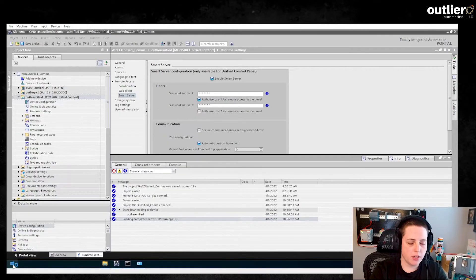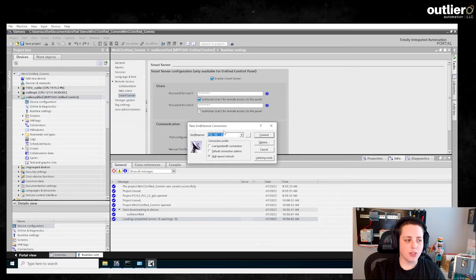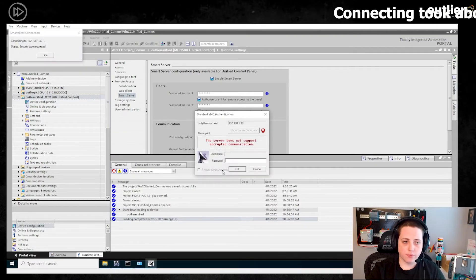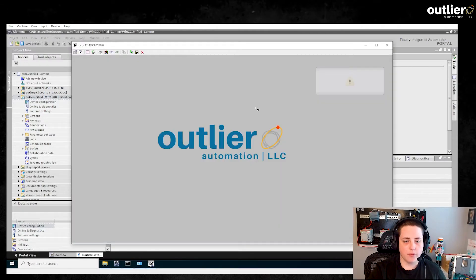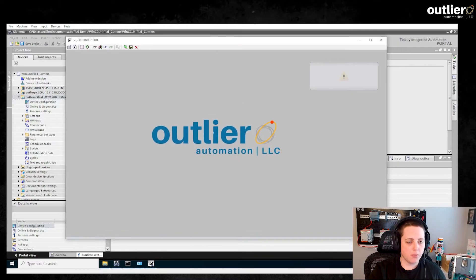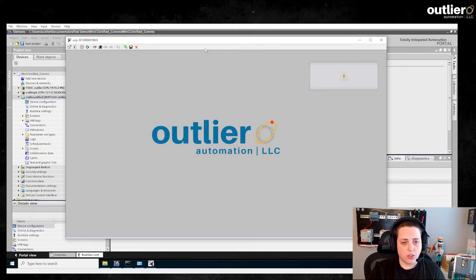I'm going to go to Smart Client, which is Siemens' built-in application for using Smart Server. But really, like I said, it's a VNC server you're enabling, so you could use any VNC client. This is a mirrored image of what's going on in the panel — if someone is operating it, you'll see their clicks. This is not a setup where you can have two separate clients controlling it; that's actually something you can set up with the web server capability on WinCC Unified, which we'll probably look at in future videos.